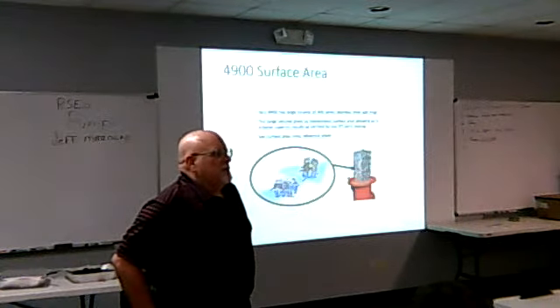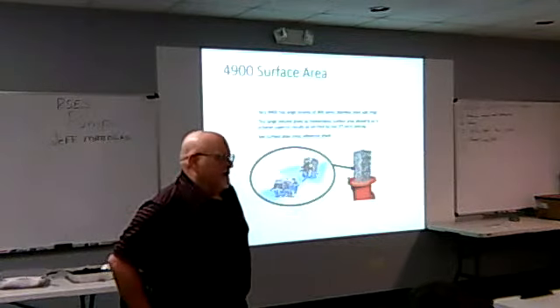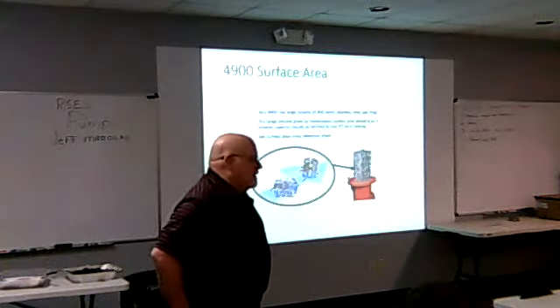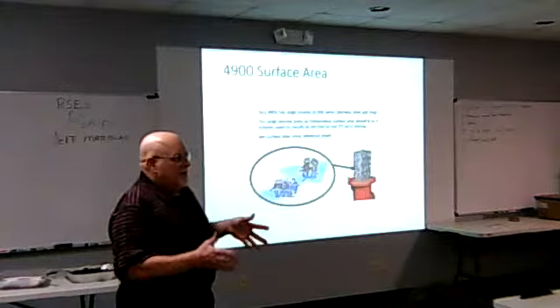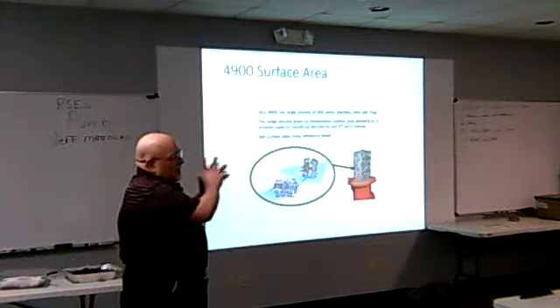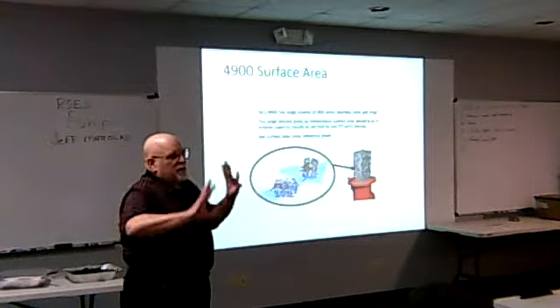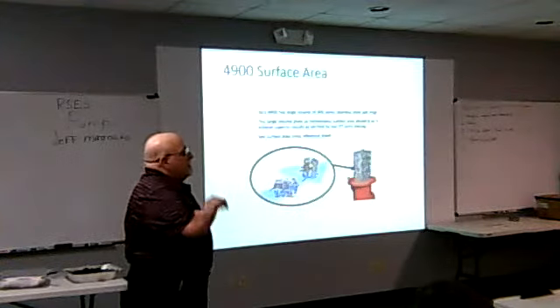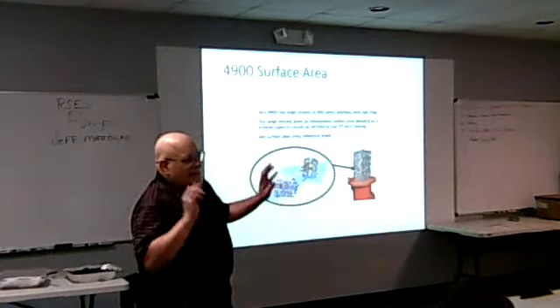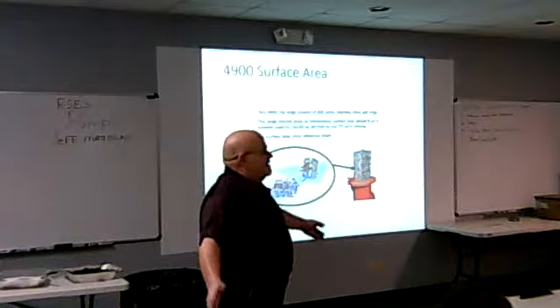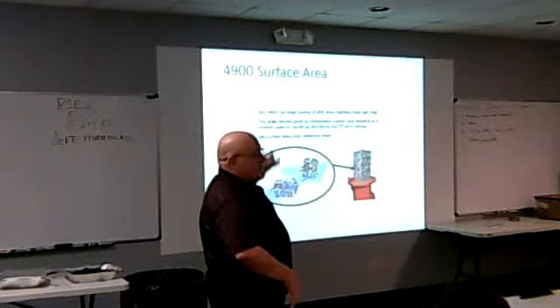Oh, here's another good thing. I ran into this the other day: condensate units. Most people don't realize. Everybody understands what system balancing is. The balancer will come in and set all the boxes and throttle the pumps to get the right GPMs. Condensate units need balance. Everybody thinks, oh, it's a condensate unit, it's at atmosphere, just push it out into the system.